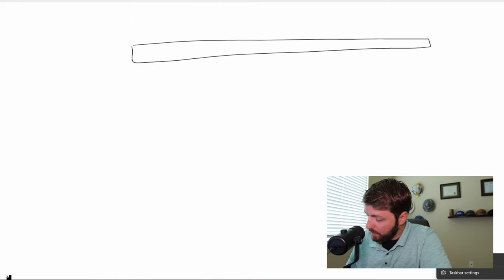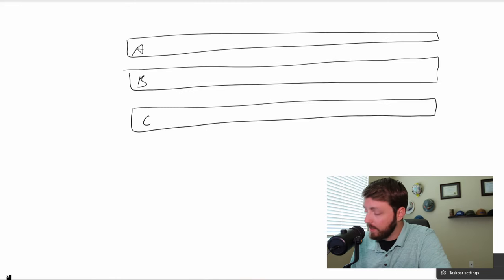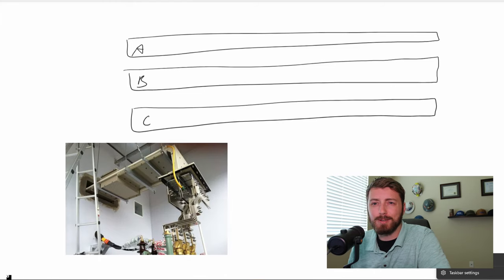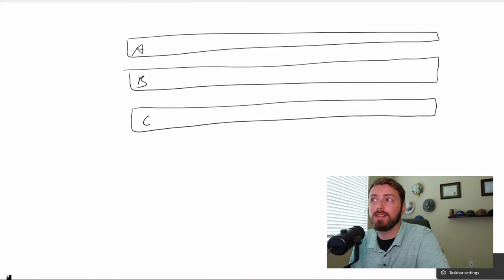The real question is, how do we ductor really, really long pieces of bus duct or metal enclosed busway, right? So what we're going to do, I'm just going to draw this real quick. Usually in a data center or some sort of large industrial site, one end is going to be a lot easier to access. It's going to be connected to a breaker, or a switchgear, something like that, where you can actually see the stub ends of that. And that's generally where I recommend hooking up the test set.